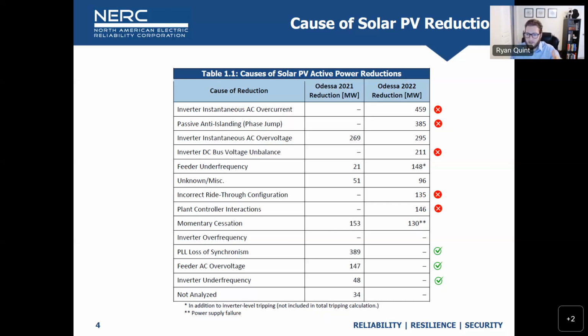The red items are things that didn't show up in the 2021 report or event, and are now very prominent in the 2022 event. These inverters and inverter-based resources as a whole are sort of like onions: you pull back the layers, and underneath you find more protections and more possible causes of abnormal performance and tripping. So we continue to uncover new things we didn't see before. A lot of folks like to reference the Blue Cut fire, but that was just one item on this page. All these other things are a compilation of what we've seen over, I've lost count now, 12 or more events that we've analyzed and published reports on.